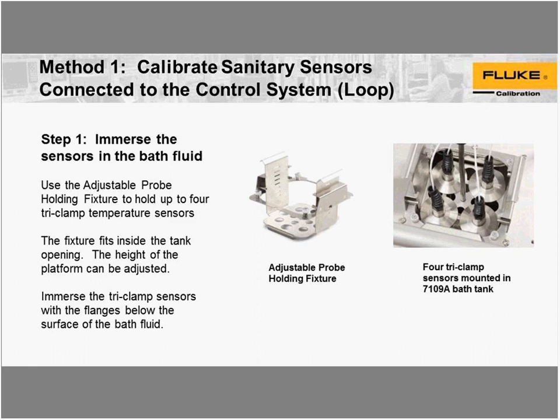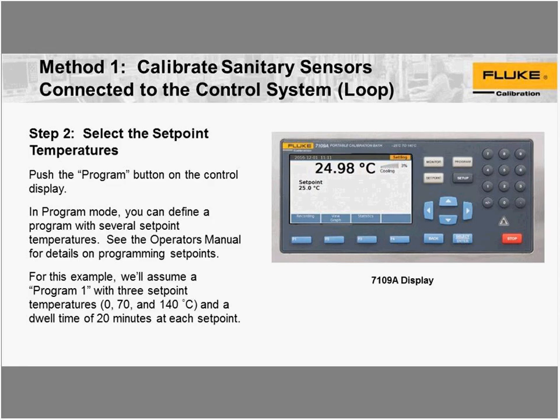Before, the typical calibration scenario was to immerse the sensor so that the flange is also in the fluid. After that, you can program in the set points you want to measure, and the tri-clamp bath will automatically sequence through them, and you can assign time to each set point and set it up in a program so it'll run through.